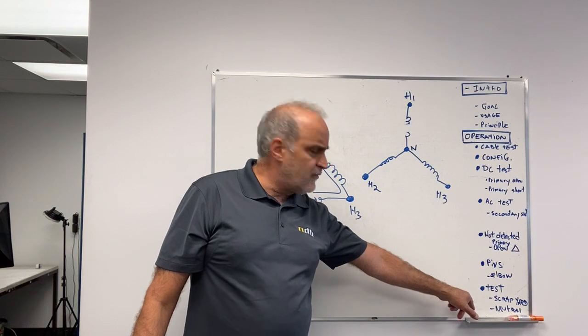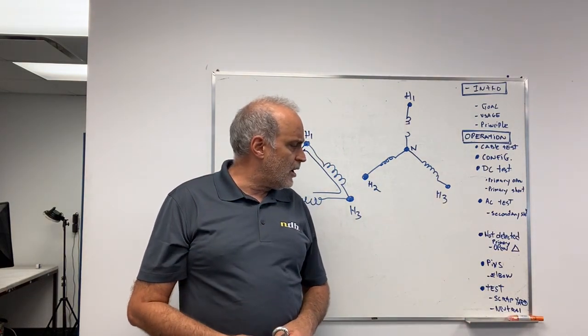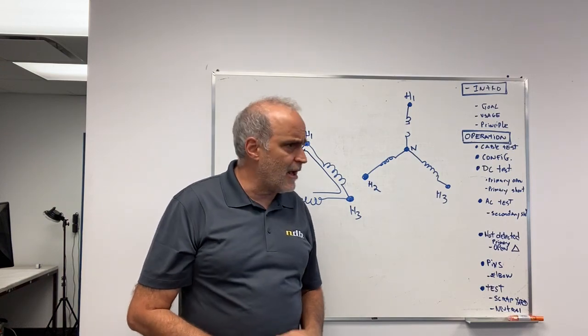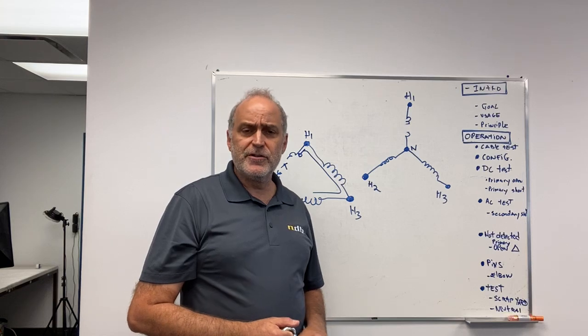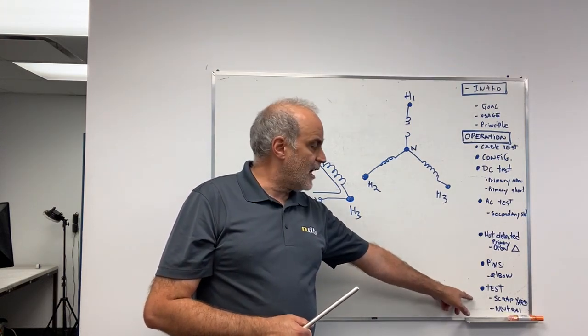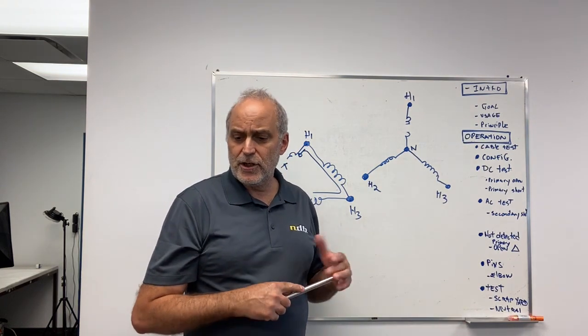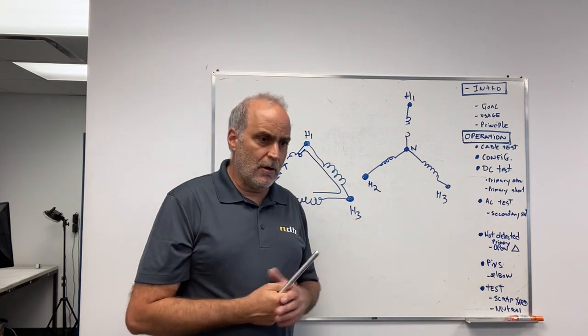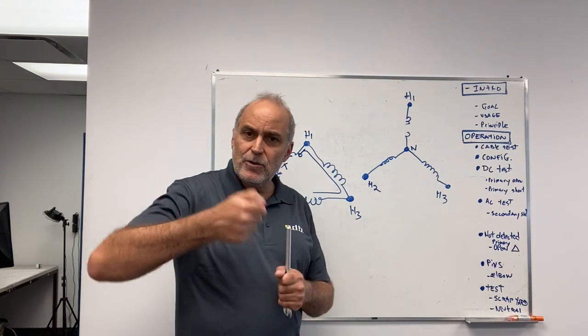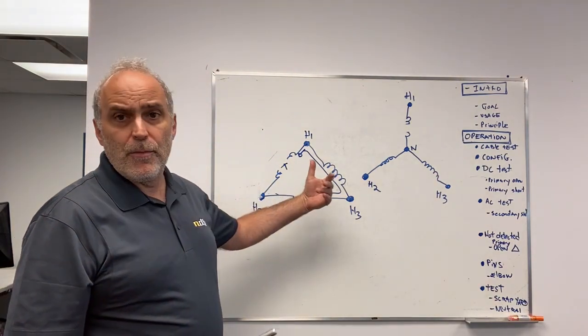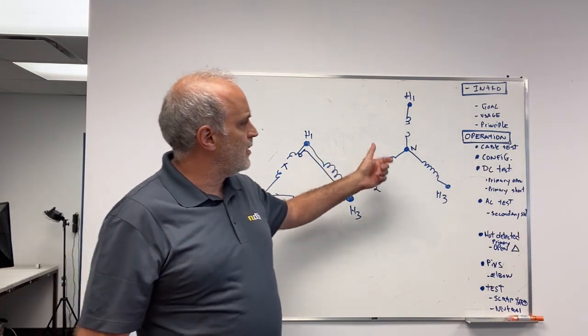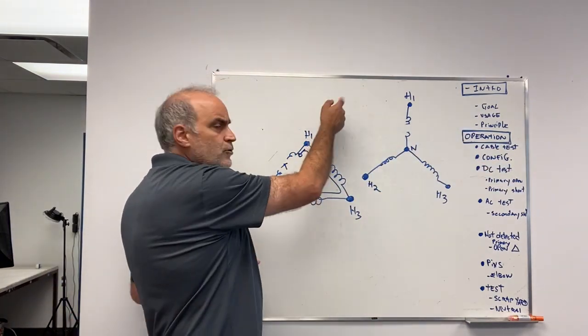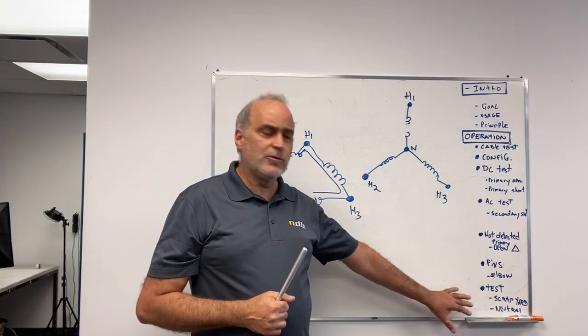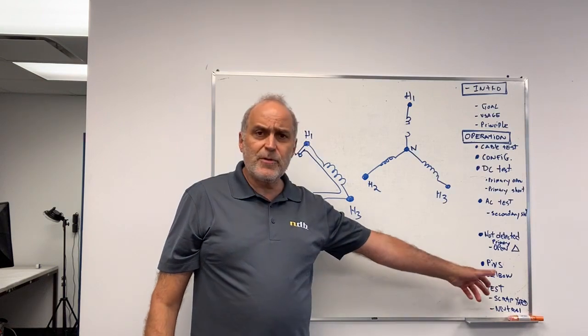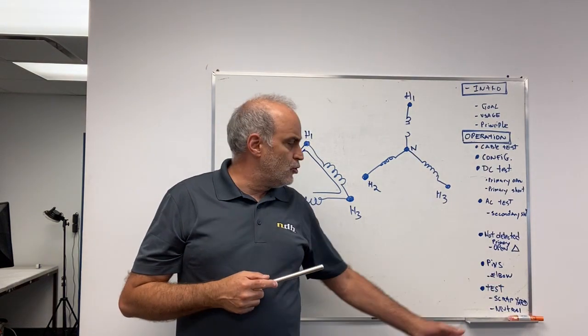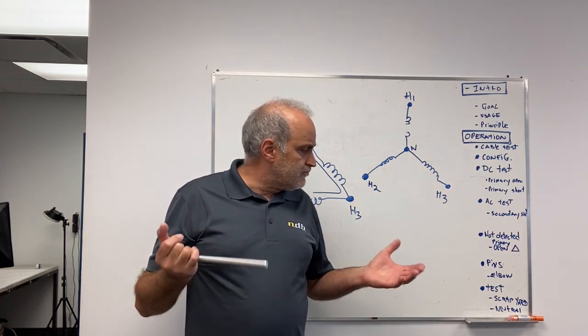Lastly, if you have access to, I'll say a scrapyard, or let's say a utility scrapyard that has a transformer scrapyard where you can make some tests, this is a nice option to start trying the duct. Or if you have a working transformer, you can simulate short or open. So you remove one clip, or you make a short on the secondary, you short H1 to ground, and so on. So you can play without going in the field. So either you go to a scrapyard, or you can try with a transformer that you own, that you have on your plant, or I don't know.